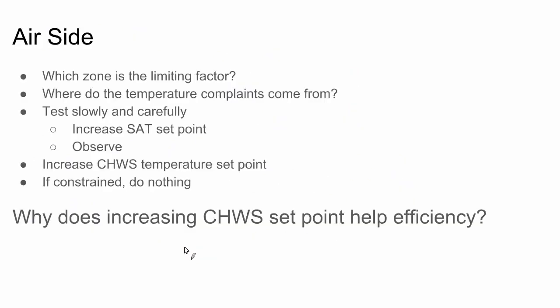So the big takeaway there is your goal on the air side is to confirm you have the ability to increase the chilled water supply temperature set point. And if you can, that's going to be an incredible help in terms of efficiency.